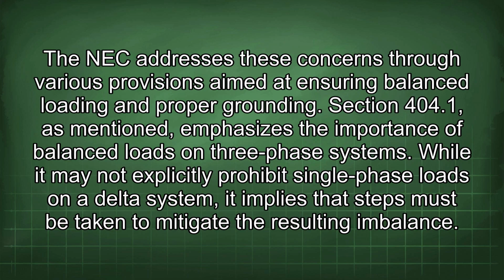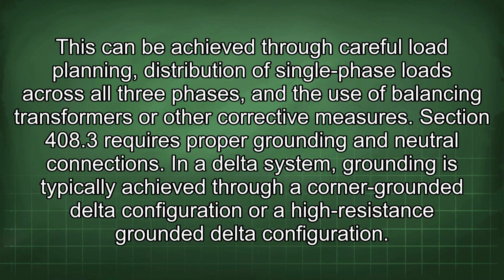The NEC addresses these concerns through various provisions aimed at ensuring balanced loading and proper grounding. Section 404.1, as mentioned, emphasizes the importance of balanced loads on three-phase systems. While it may not explicitly prohibit single-phase loads on a delta system, it implies that steps must be taken to mitigate the resulting imbalance. This can be achieved through careful load planning, distribution of single-phase loads across all three phases, and the use of balancing transformers or other corrective measures.